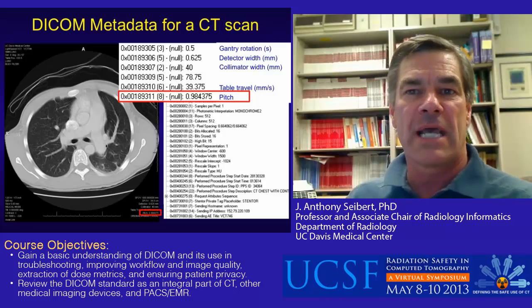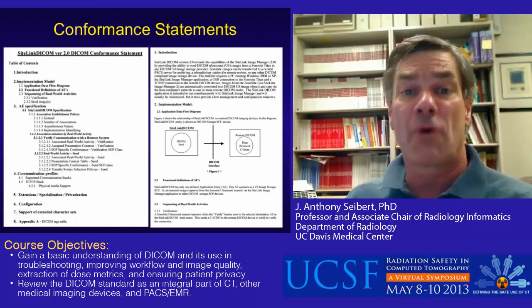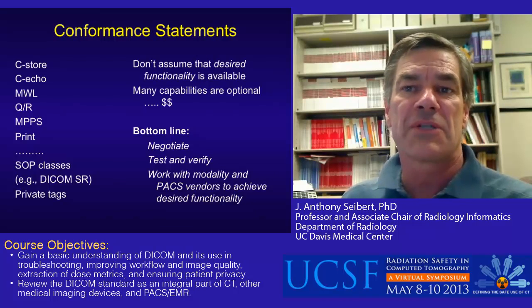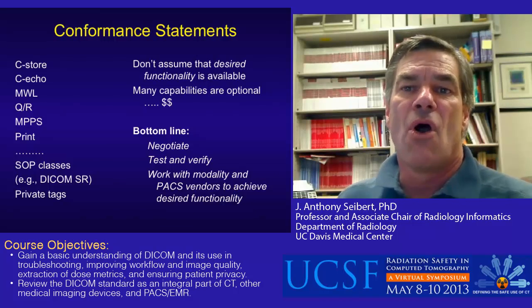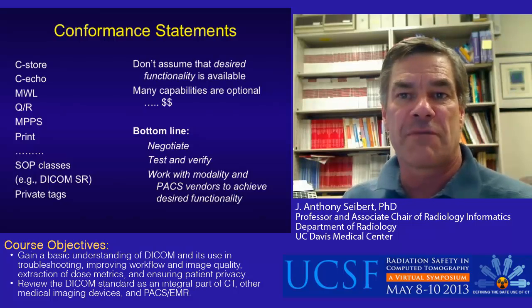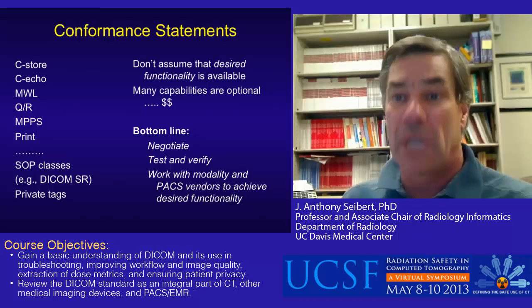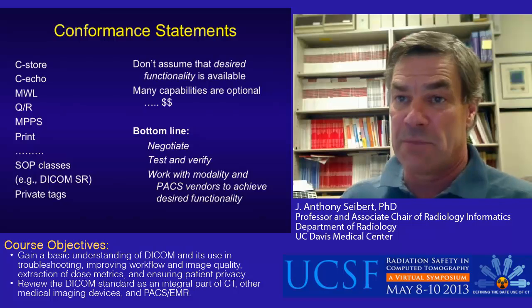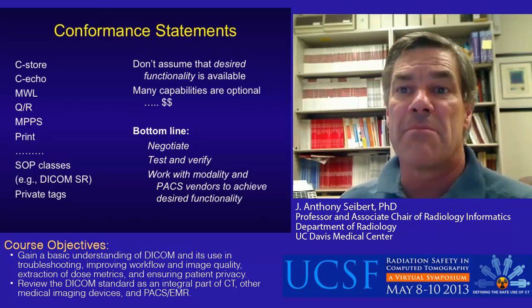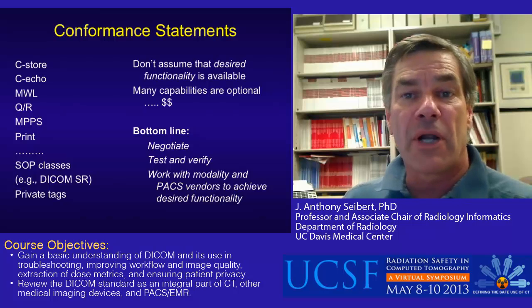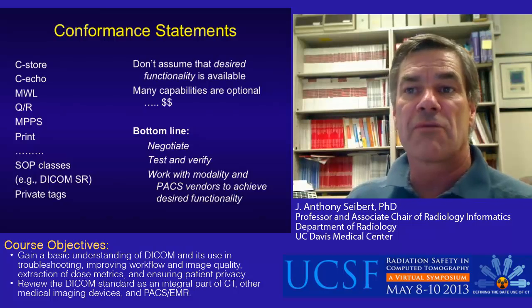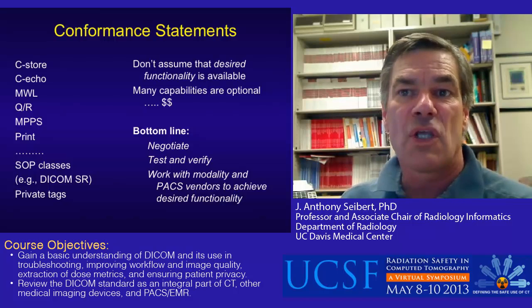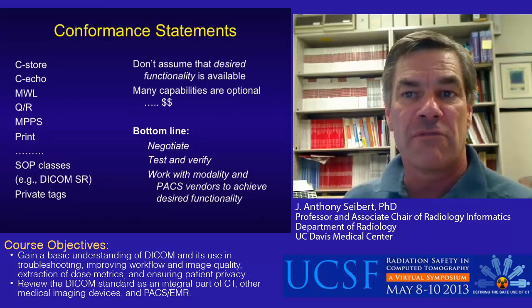How does one find out about the tags, attributes, and value representations? That is where the DICOM conformance statement comes in. A conformance statement is a lengthy document that explicitly describes the details of DICOM implementation by a manufacturer, where details of the implementation model, application entity specifications, communications protocols and profiles, DICOM tags, and other information are published. DICOM conformance statements detail the services and functionality provided by the modality vendor and the PACS vendor. However, many functions are optional and must be negotiated at extra cost, so you must work with both the modality and PACS vendors to ensure and achieve desired functionality.